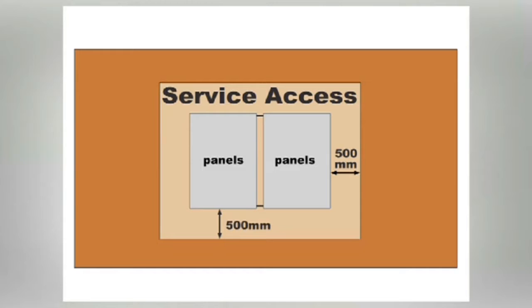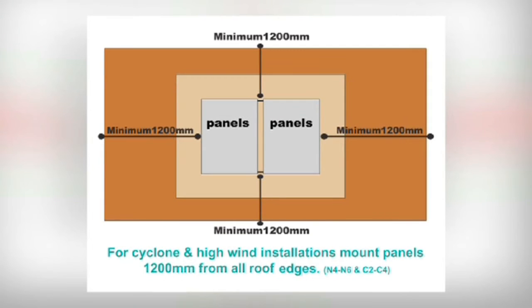This slide shows the importance of set out by leaving 500 millimeters clear around the panels to allow for service, and allowing for high wind situations by keeping the bottom of the panels 1200 millimeters from all roof edges.